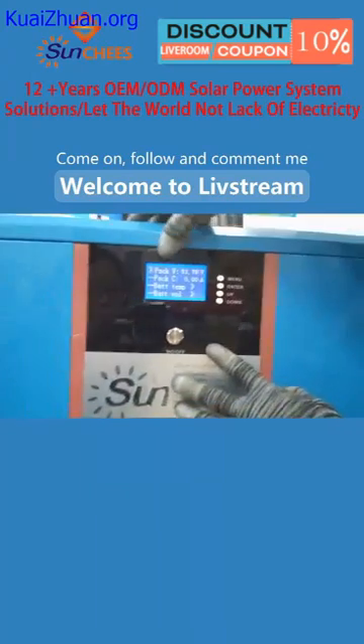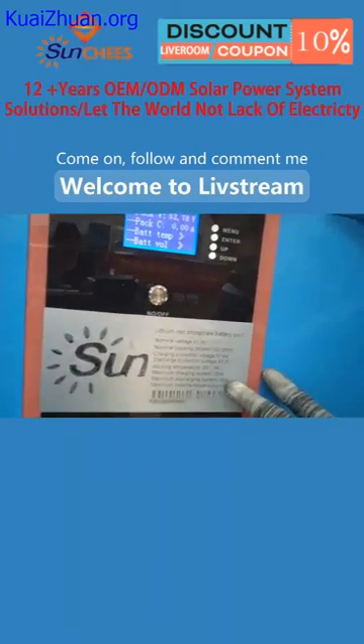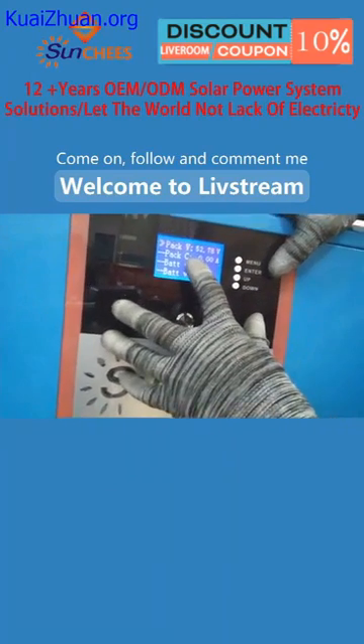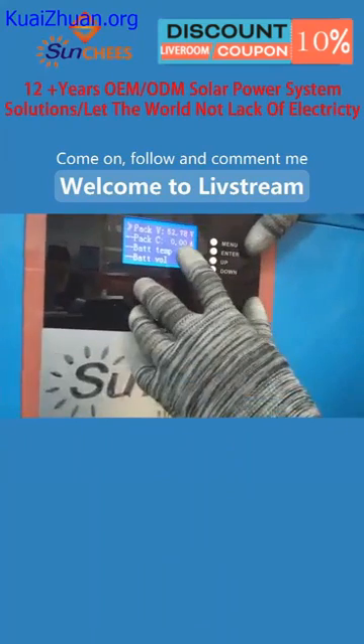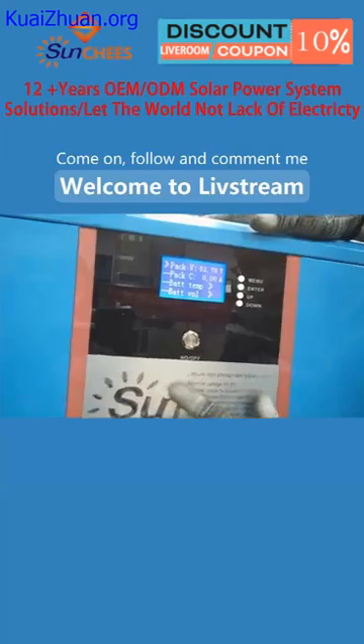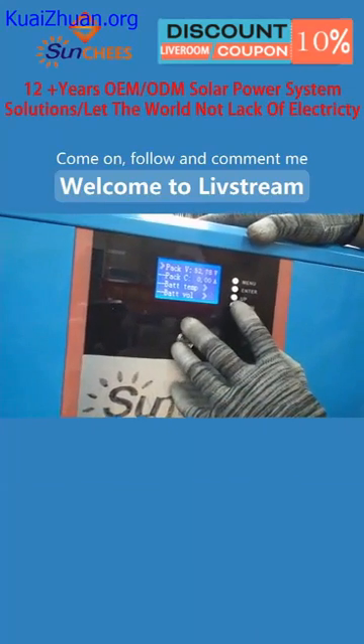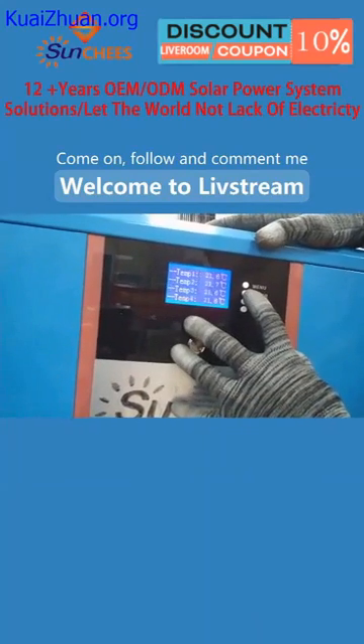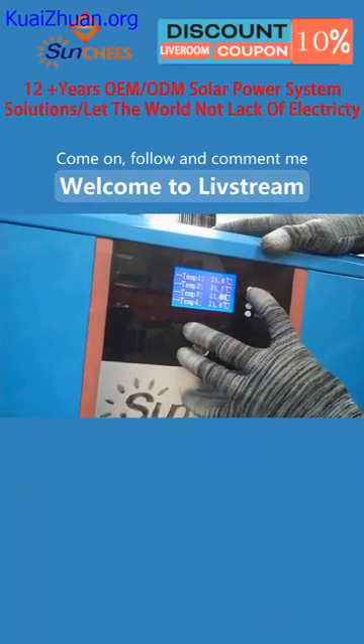Enter. Now the battery bank voltage right now is 52.78 volt. And on the second line you can see the output current. Right now the output current is 0 ampere because the lithium battery bank is not connected to anything. And you still can check the battery temperature. See, there are 4 temperatures. And then we go out.